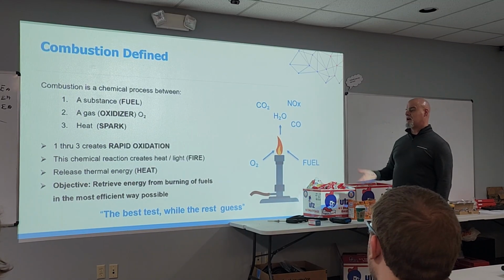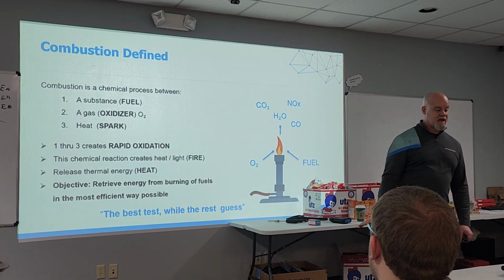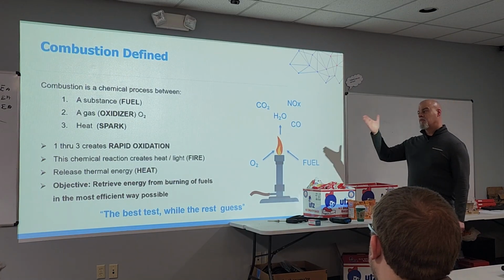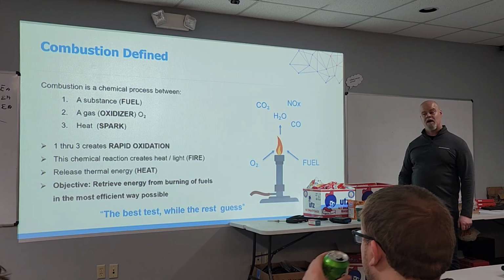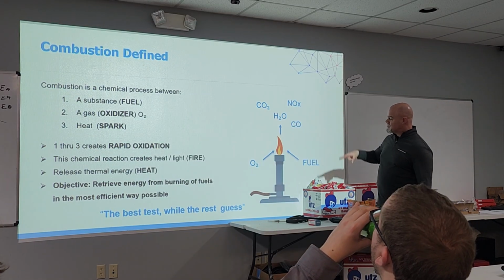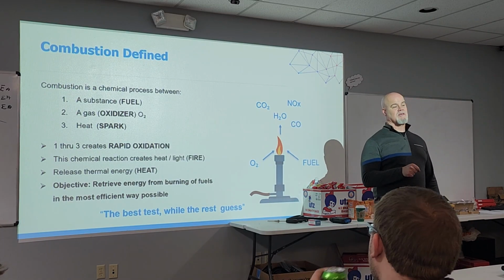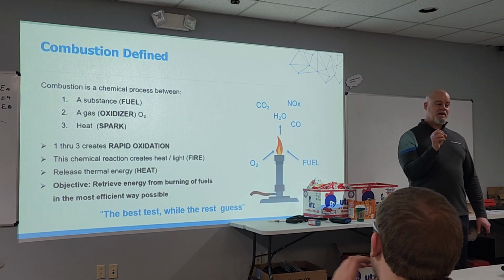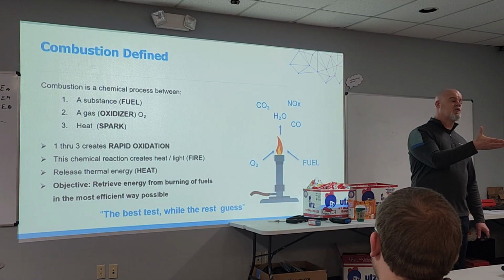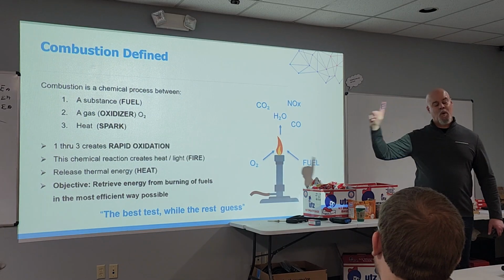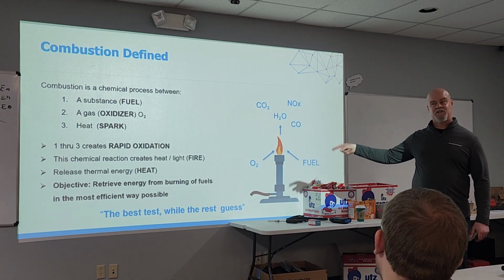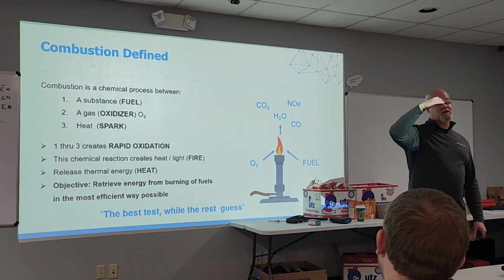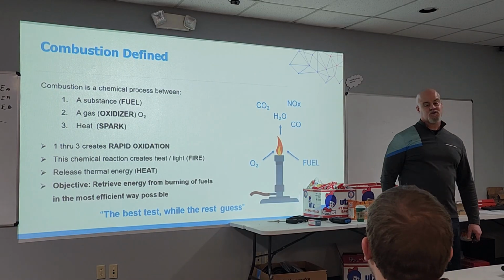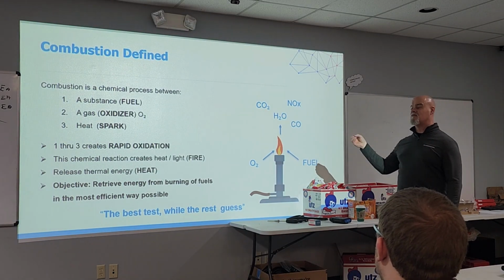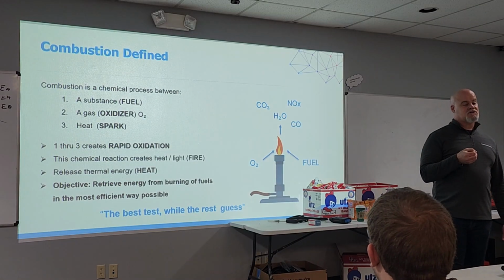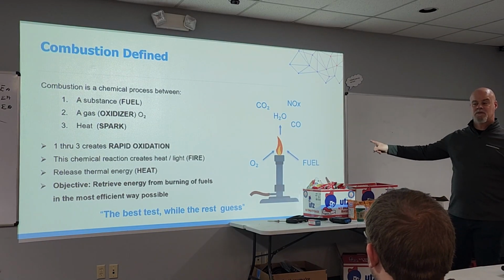So when we do combustion tests, we're doing the blood pressure on that system by doing the gas pressure, but we're also doing the blood work on it by doing its full panel, its combustion analysis. And we can know, based on these numbers, how that patient's health is, and then what remedy or solution to put it on. Your doctor puts you on a protocol to lessen your cholesterol, fine - we can adjust things in the system to drop that overfire condition and lower that carbon monoxide. So you've essentially become a concierge medicine doctor, but your patient is per system.